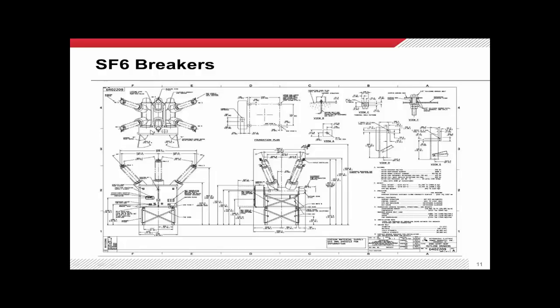Your frame of reference is built around where your control cabinet is, and not every manufacturer uses the same scheme. I once did a project where I thought I was getting one manufacturer's breakers, but at the last minute it changed to a different manufacturer. Every single circuit breaker's CT wiring was backwards, and they had to rearrange the design in the field. I bring this up to illustrate the importance of that one facet.